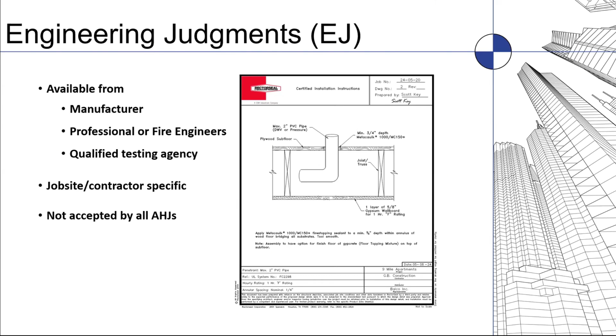The specification area for Firestop, the general section used in the CSI master format, is 078400. That's the primary section for fire stopping. There are two categories in there: one for penetrations and one for joints. So 078413 is penetration fire stopping, and 078443 is for joint fire stopping.